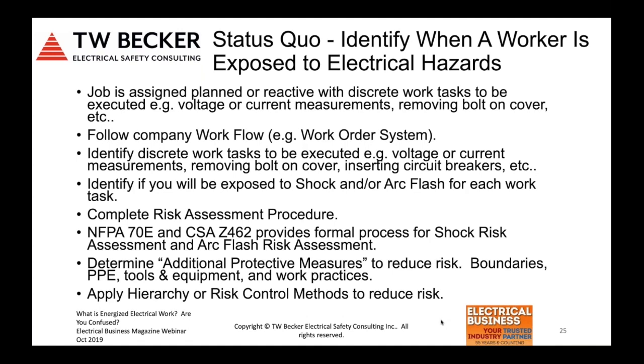Now, this is the context of Z462 and 70E, and with respect to, again, the status quo, because we've had Z462 in Canada now for over 9 years, and 70E's been in the US for a long time, but the latest edition of both those standards would require a risk assessment procedure and individual shock and arc flash risk assessments, and then determine additional protective measures to reduce risk: boundaries, PPE, tools and equipment, and work practices, and apply ultimately the hierarchy of risk controls to reduce risk. So I'm saying this is the status quo.